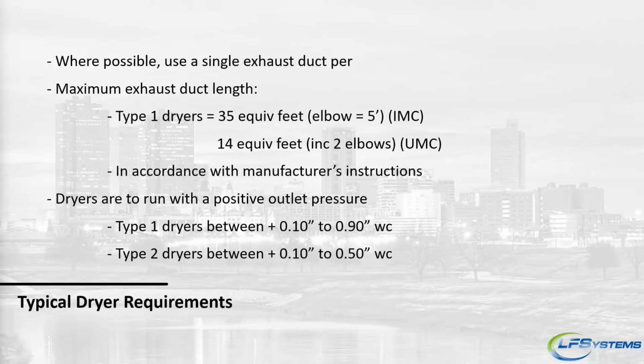Maximum length on a type 1 dryer is 35 feet according to the IMC, or 14 feet with 2 elbows according to the UMC. Basically, an elbow equates to about 5 feet in that equation. So depending on which code you follow, you have to look at that. The other option is to follow the manufacturer's instructions. So if you have a residential dryer that says that you can go beyond that 35 feet, you can do that.